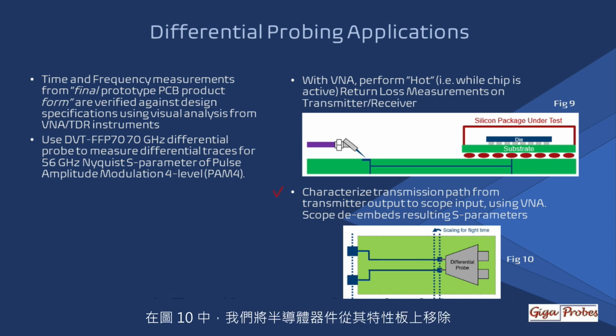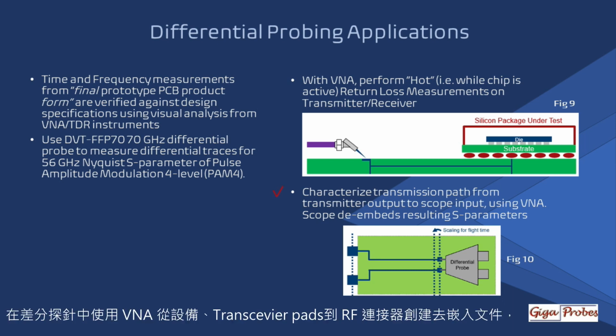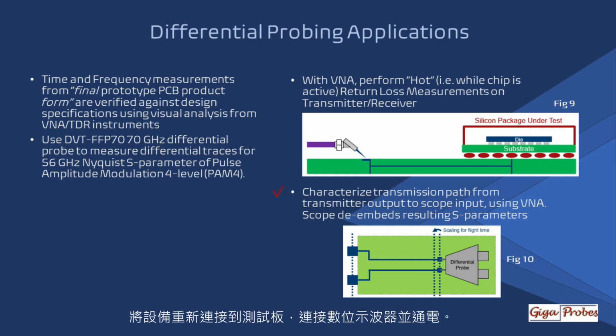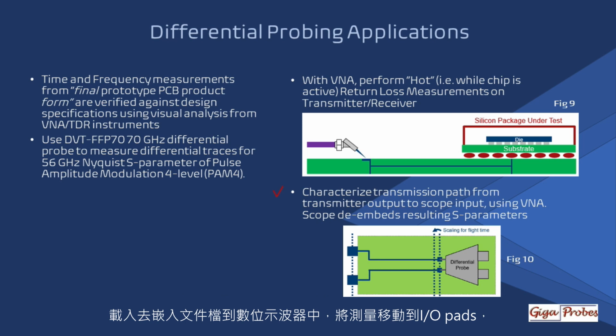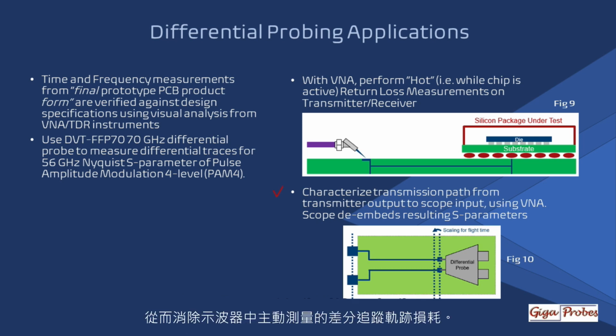In Figure 10, we remove the semiconductor device from its characterization board. Use a VNA and a differential probe to create a de-embedding file from the device transceiver pads to the RF connectors. Reattach the device to the test board, connect a digital oscilloscope, and apply power. Load the de-embedding file into the digital oscilloscope to move the measurement to the I/O pads, thus eliminating the differential trace loss from the active measurements in the oscilloscope.